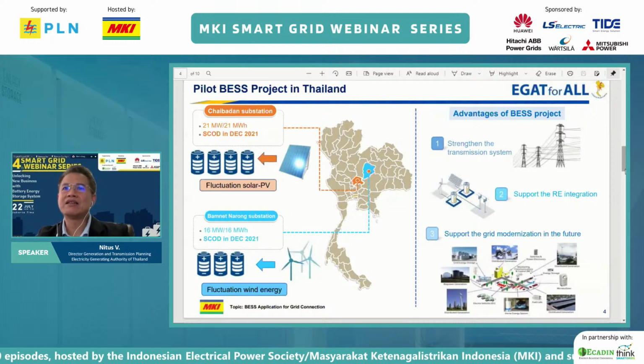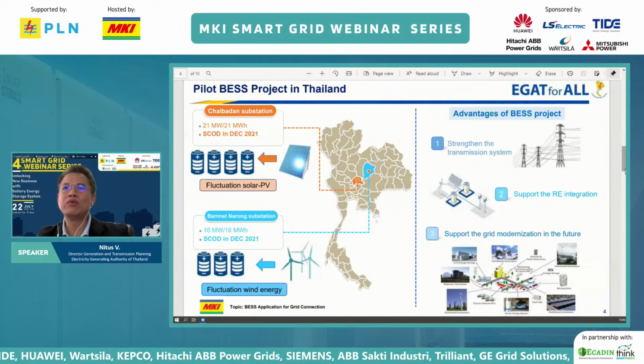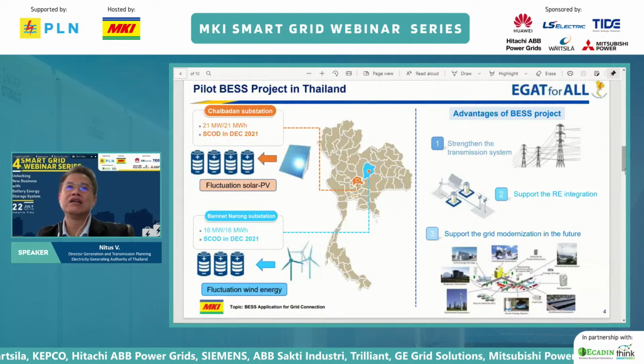For the Chai Badan substation, there is a lot of solar PV in this area. The objective of the BESS is to prevent fluctuation in solar PV. Therefore, a 21 megawatt, 1C rated BESS was decided to be installed for the solar PV in this area.